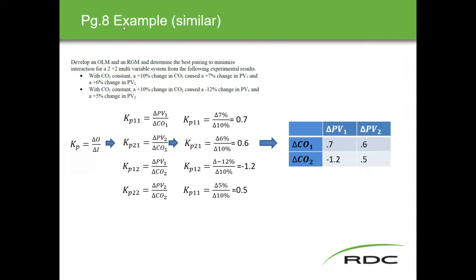This next example is very similar to the one in the self-test. I wanted to include it so you'd have a good idea of what the wording looks like in that type of question and how to get there using simpler values. The question is: develop an OLM and an RGM, and determine the best pairing to minimize interaction for a two-by-two system. Controller two is held constant, then a 10% change is made in CO1, causing a 7% change in PV1 and a 6% change in PV2.